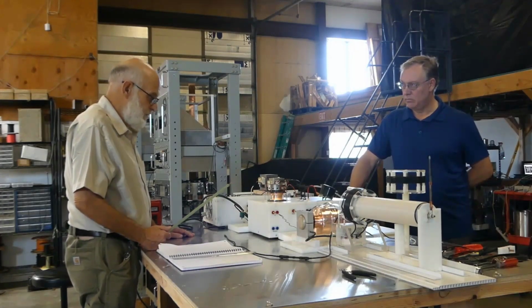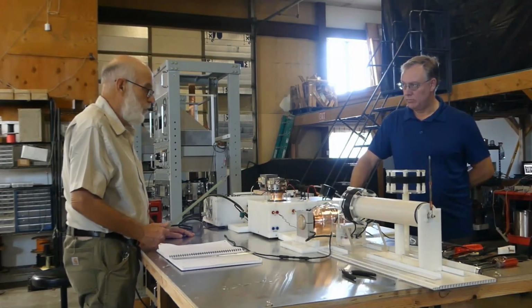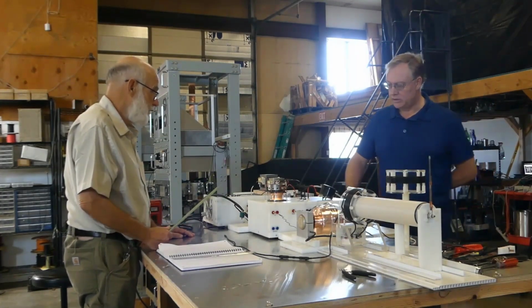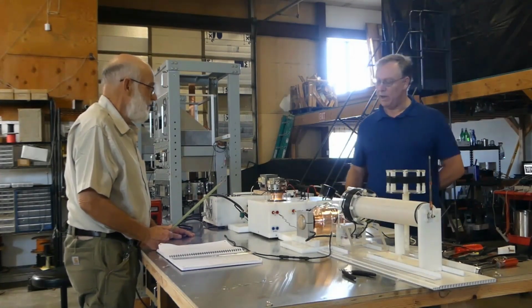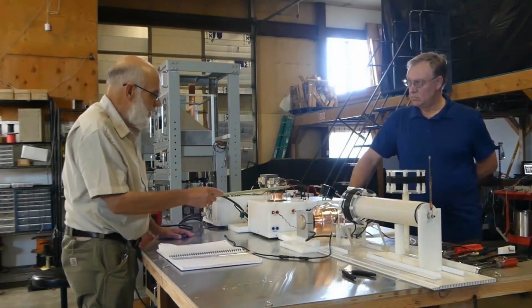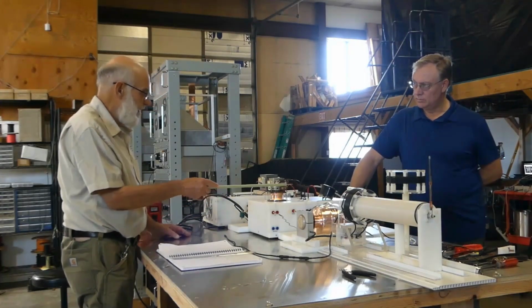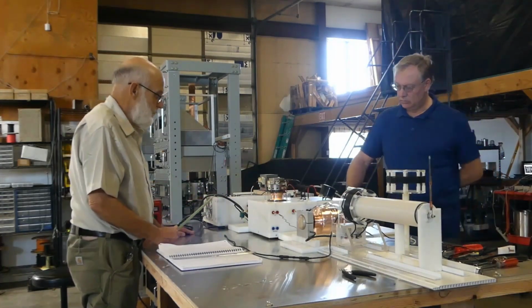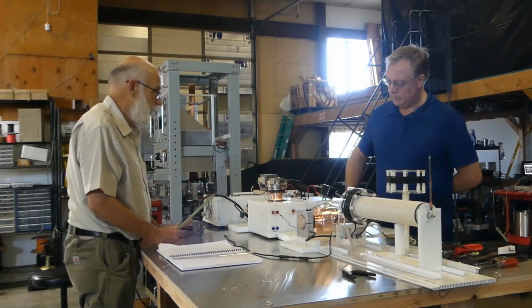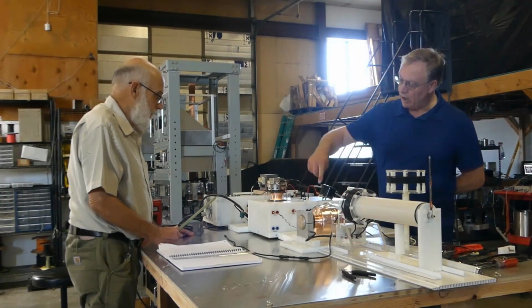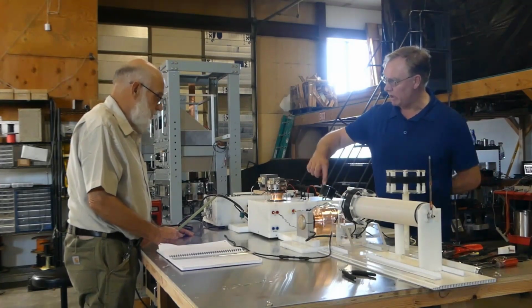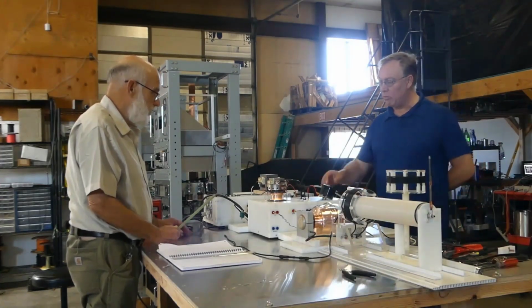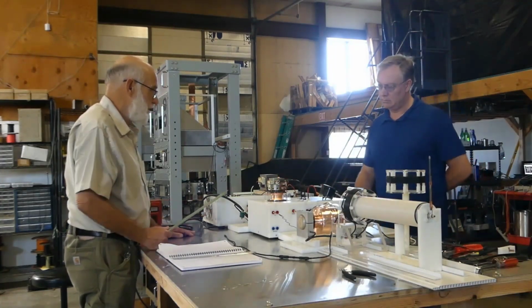That's why you can't use any iron hardware around your high power RF stuff. So it's like a magnetic damper, an impeder. Basically, any high frequency oscillation is going to see this thing as a resistor, pretty much an open circuit. So this iron coil here is going to damp out all of the oscillations that might occur in that grid, and prevent them from getting going. That will stop the tube from oscillating. It's what's called a parasitic suppressor.